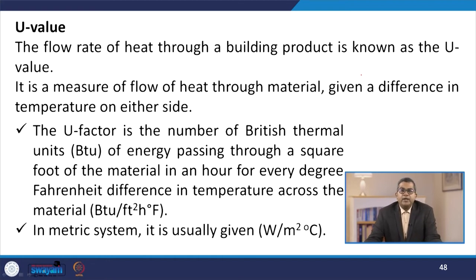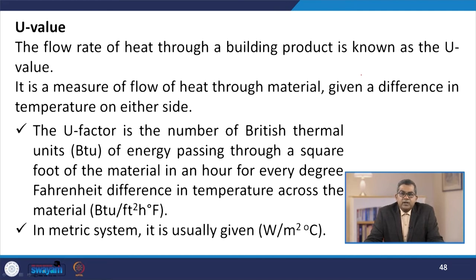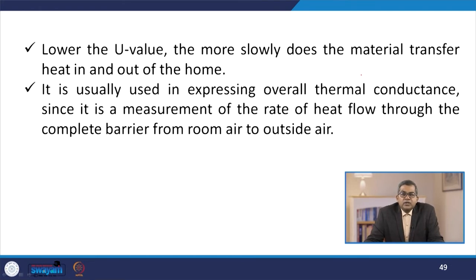The U value is the flow rate of heat through a building product — a measure of flow of heat through a material given a different temperature on either side. The U factor is the number of BTU of energy passing through a square foot of material in an hour for every degree Fahrenheit difference in temperature across the material (BTU per ft²·hr·°F). In the metric system, it is given as W/m²·°C. A lower U value means the material transfers heat more slowly into and out of the home.